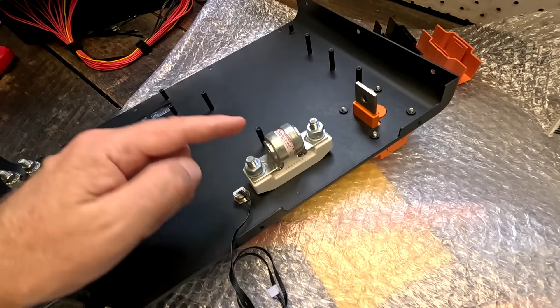The 250 amp rating here is fine because this fuse protects from a direct short, and with such a battery we have definitely more than 250 amps, so it will trip very quickly. And with 100,000 amps of breaking capacity, very, very good choice of a fuse, Mr. EEL.